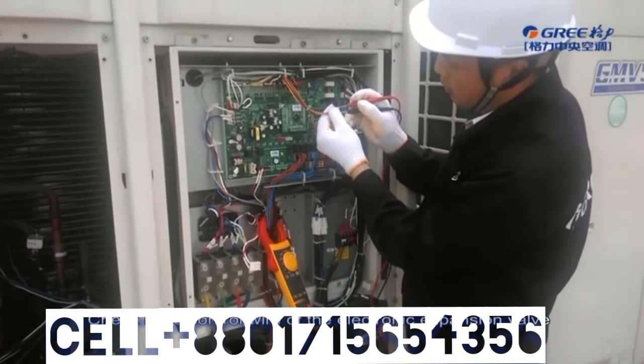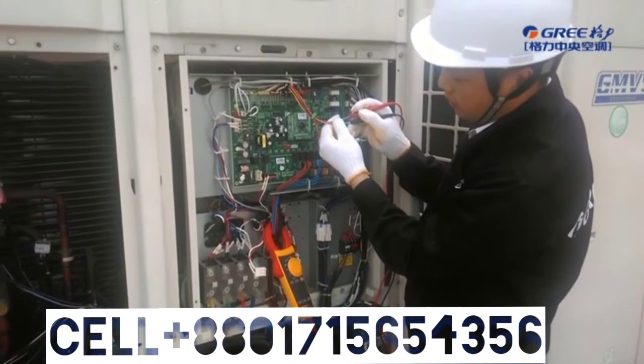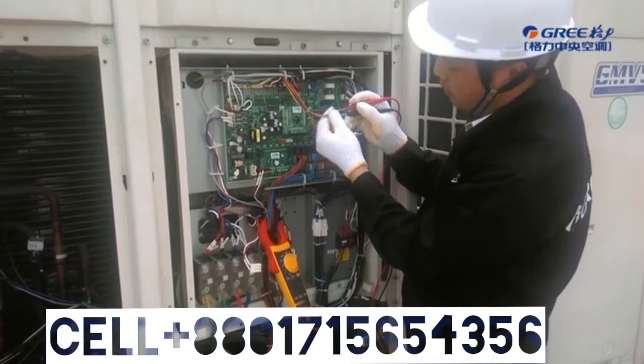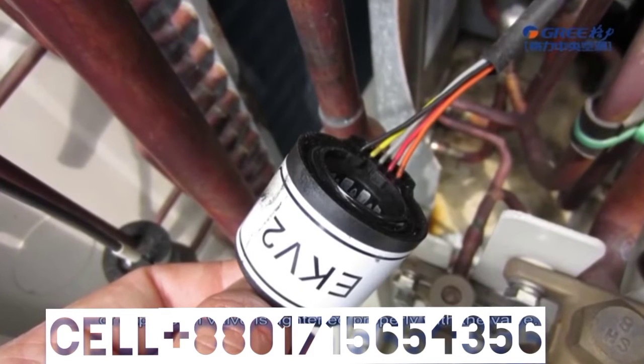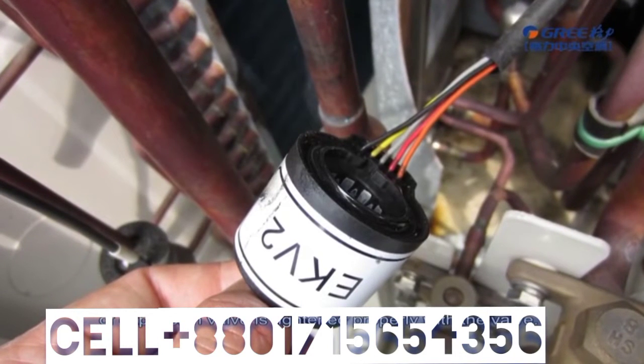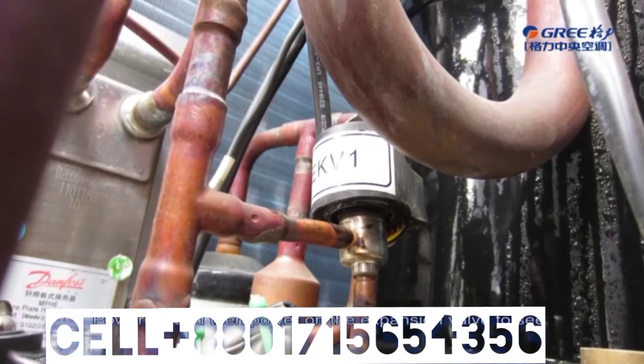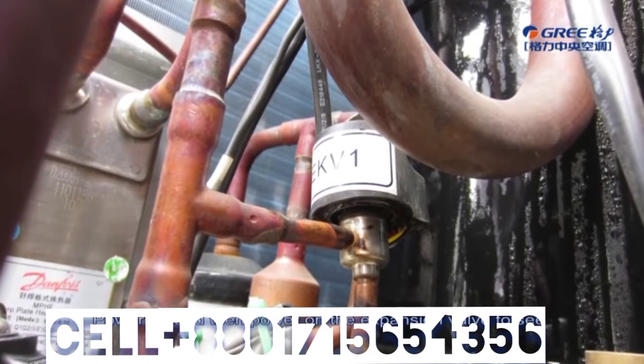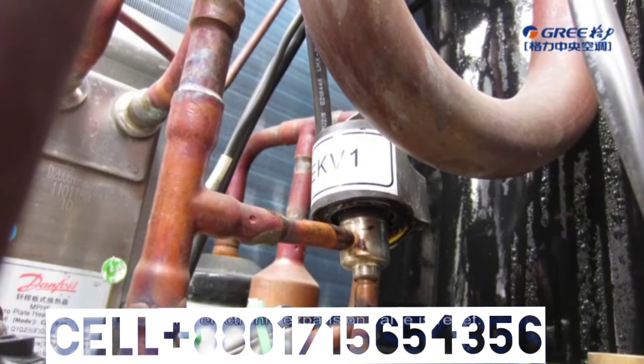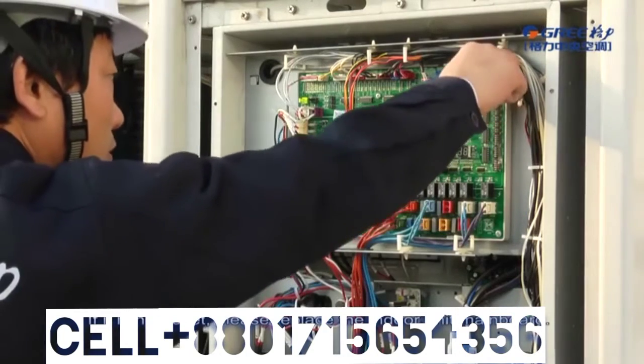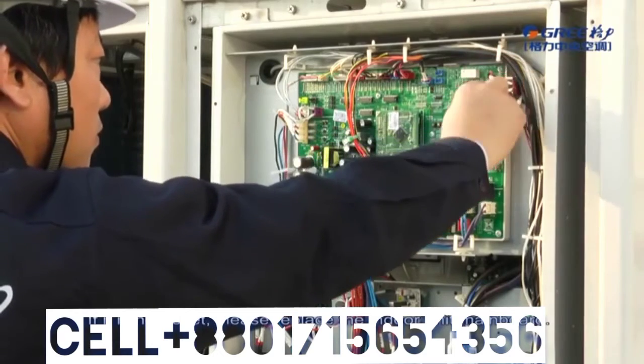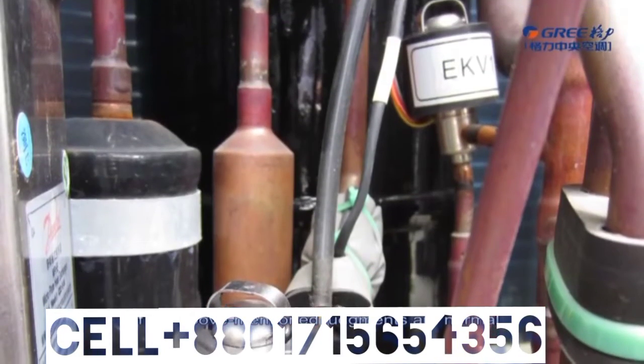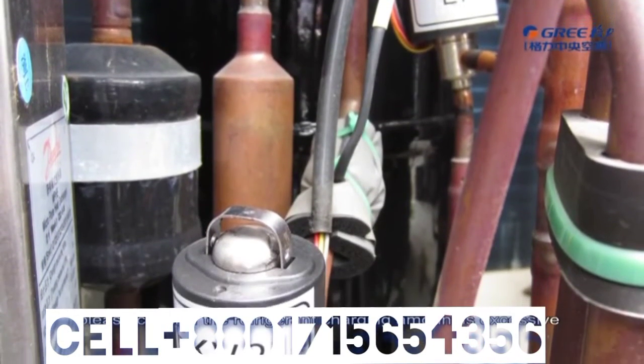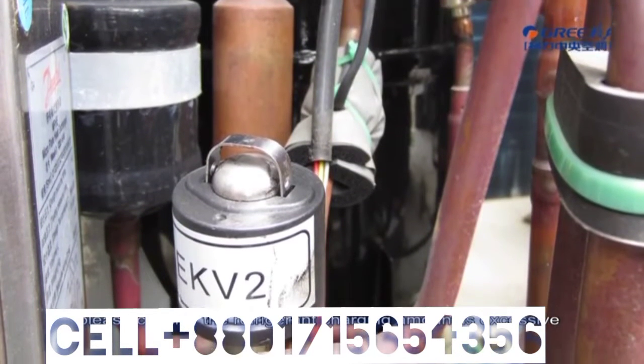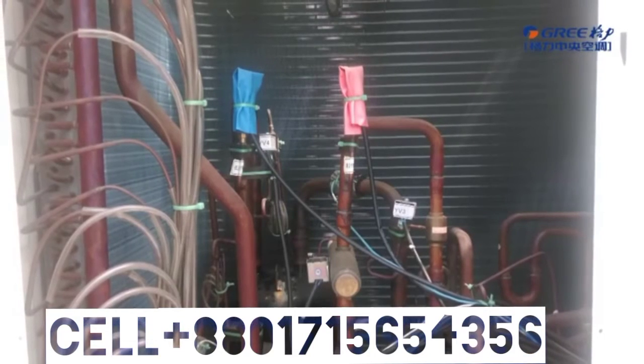Check if the control wire of the electronic expansion valve is connected well to the mainboard, and if the coil of expansion valve is tightened properly with the valve. Power off and then power on the electronic expansion valve to see if the electronic expansion valve is reset. If it is not reset, please replace the outdoor unit mainboard. If the above-mentioned adjustments are normal, please check if the refrigerant charging amount is excessive.